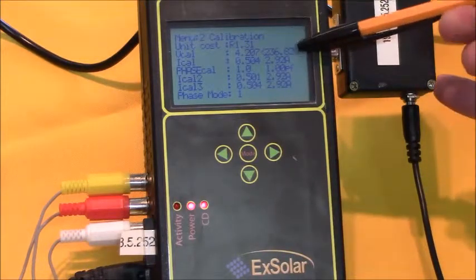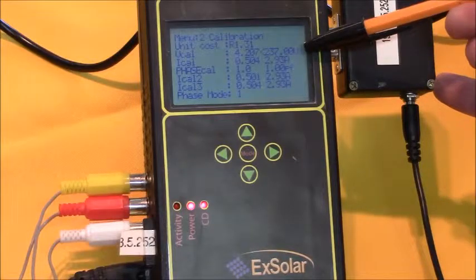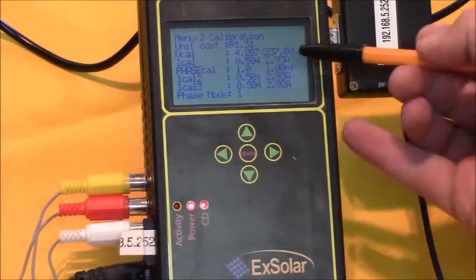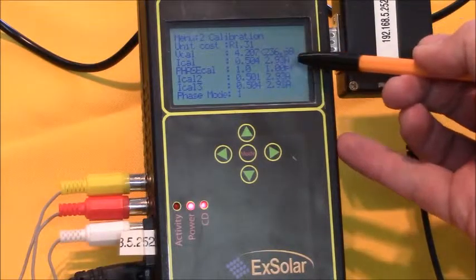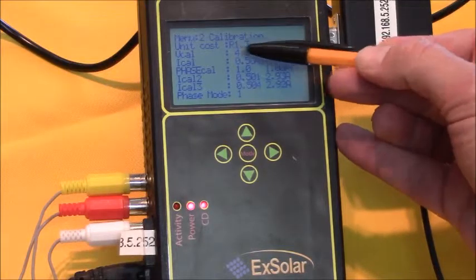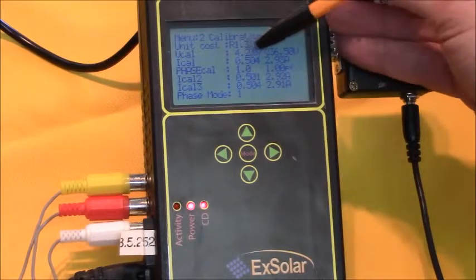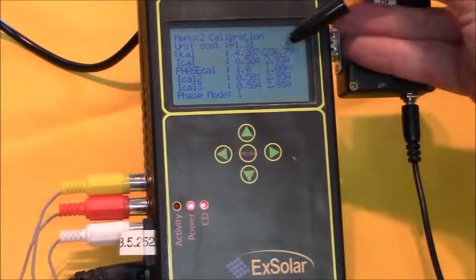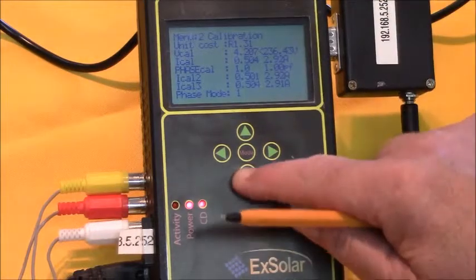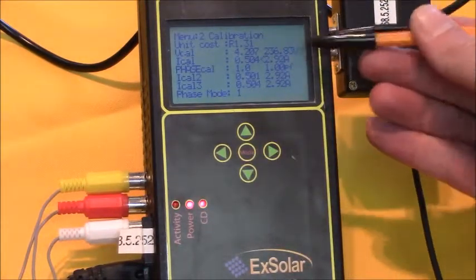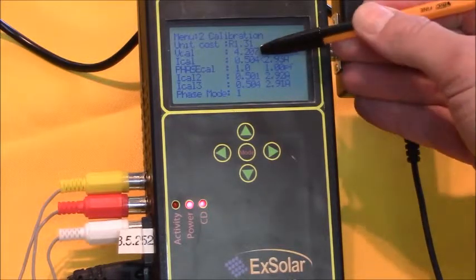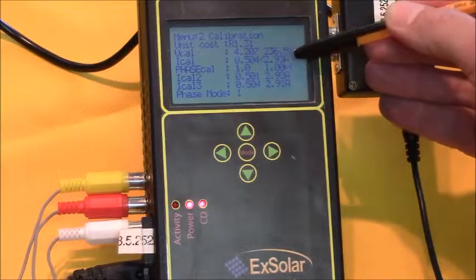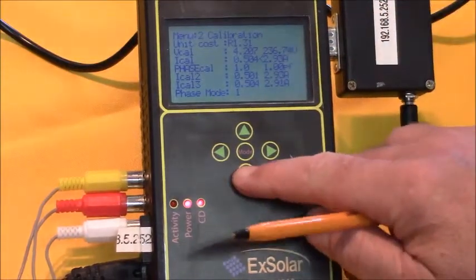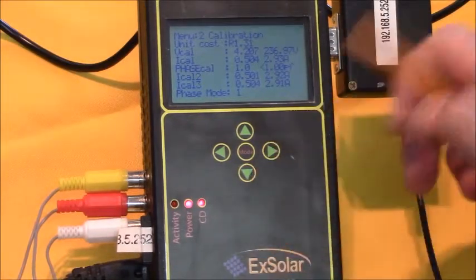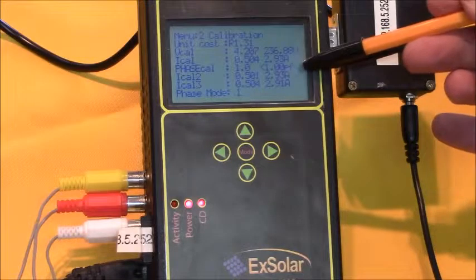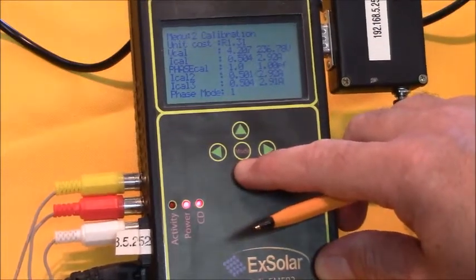The voltage calibration, that is the voltage which is sensed at this point. And if you see here, it is sitting at 236.68 volts, and that is the relative calibration figure. So that is the figure that we would change in order to match the Fluke. I'll show you that in a minute. Going down, the current calibration is showing a current of 2.93 amps, and that's the relative offset which is required to match the Fluke. The power factor, because we've got a purely resistive load, is normally set to 1, and you generally don't have to change that. And then for the other two sensors, same story.